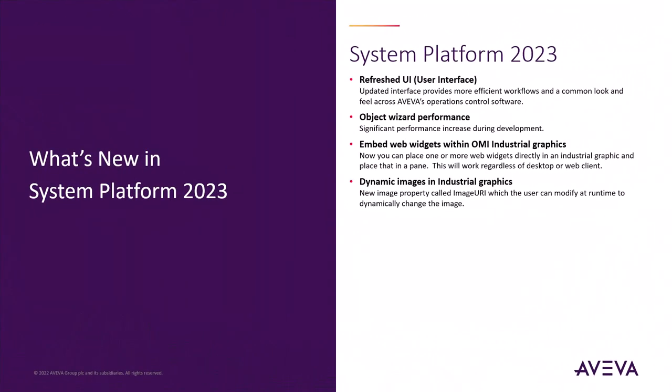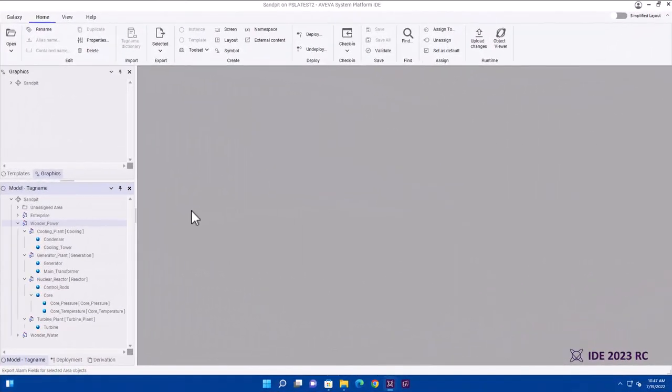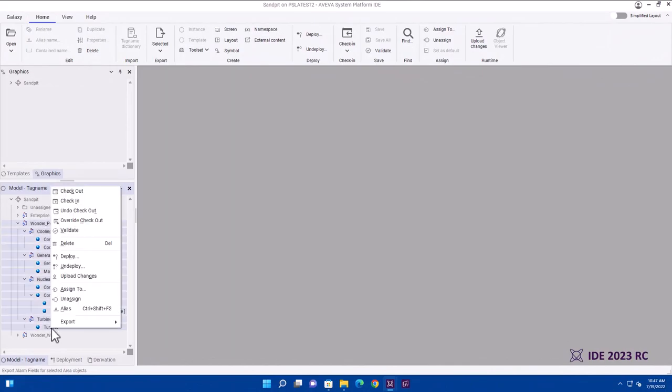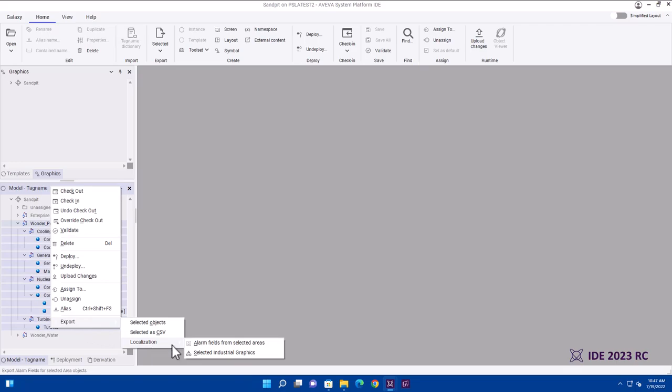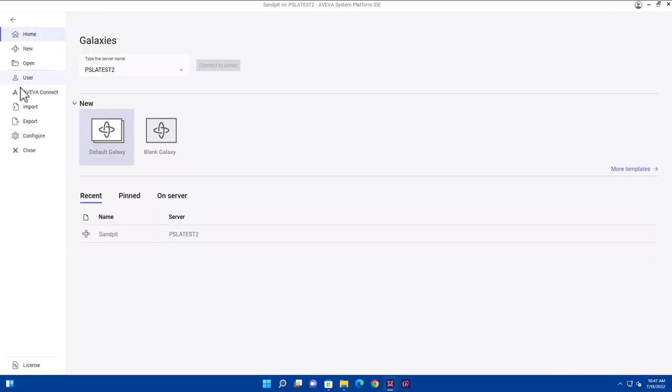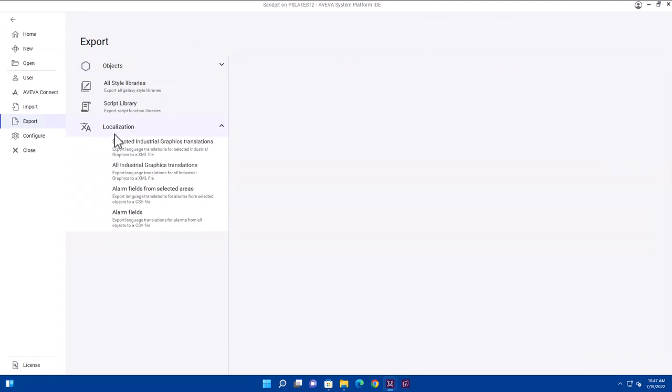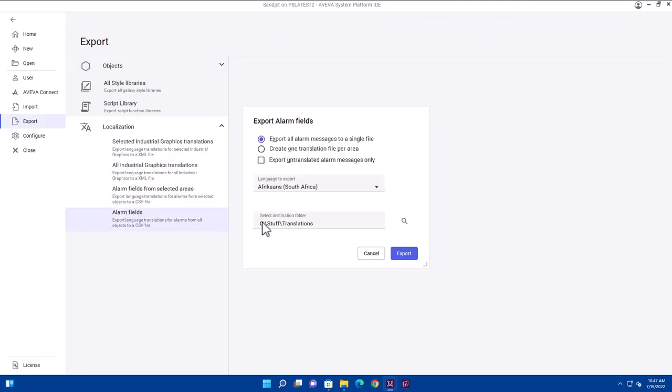We made some improvements to our alarming capabilities. Firstly, we expanded the translation capability of the alarm app. In System Platform 2023 IDE, I can create a translation file by selecting the objects, right-clicking Export Localization, and select Alarm Fields, or I can use the backstage and just simply go and export localization and all the alarm fields available to me.